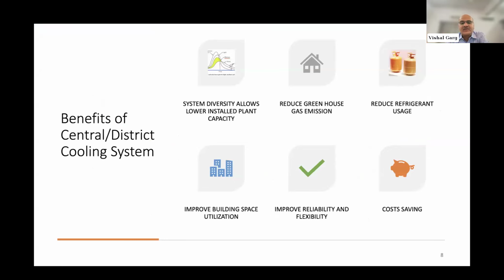And then it improves the building space utilization. You don't have these hanging outdoor units everywhere. It can reduce the emissions. There would be less refrigerant use, so less leakages and proper control of the equipment, more reliability, a lot of flexibility, enjoying diversity and providing flexibility to all the spaces. And it can also lead to cost savings, not only in terms of capex by reduced chiller size, but it can also lead to reduced opex because it is operating at a very high efficiency.